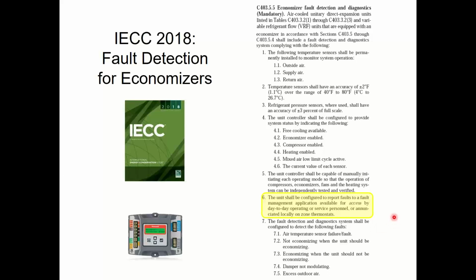It's going to flash service fault or equipment failure or something like that. The occupant's not going to know what the hell that means. They're going to call their HVAC guy. He's going to walk in and look at the thermostat and say, yeah, you got a fault. Cool. He's going to walk up to the roof, open up the cabinet, and then he's going to look at this controller screen and see what the specific fault is. Maybe it's the supply sensor's out of whack, right? It's reading like -13. Well, that's obviously not right. Right, so we got to fix that sensor.